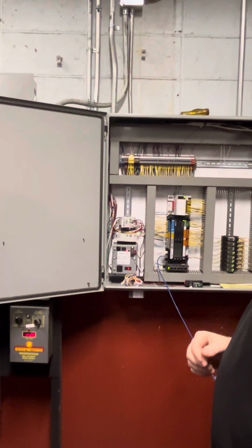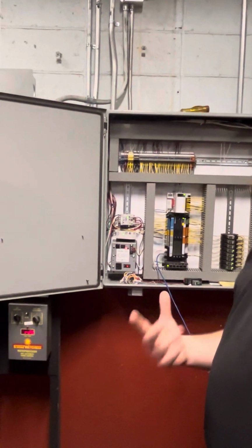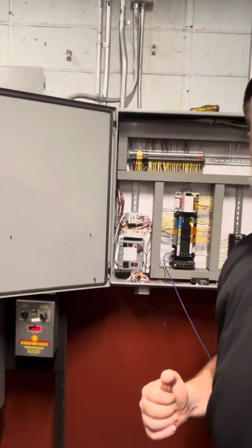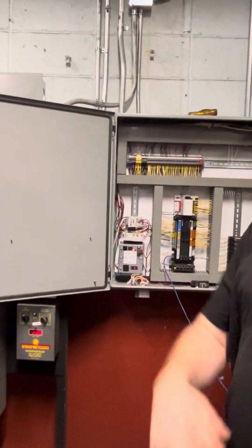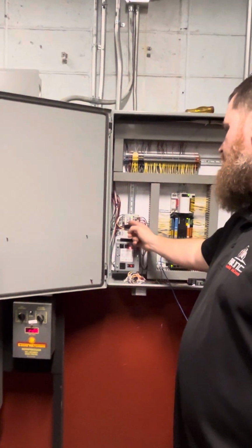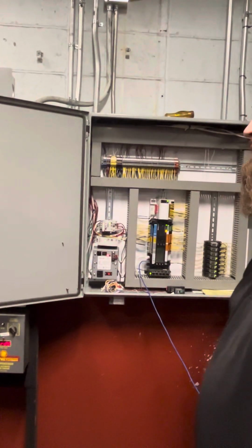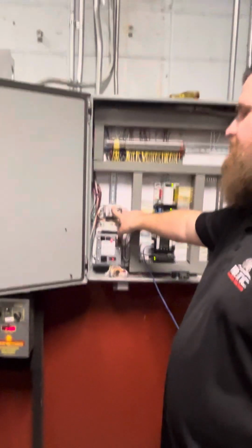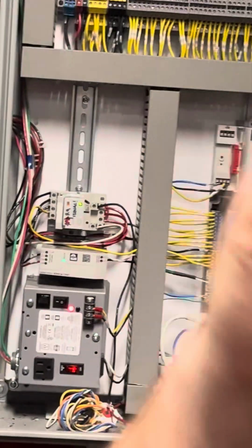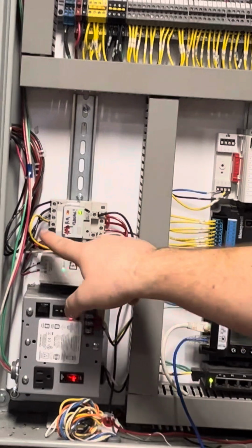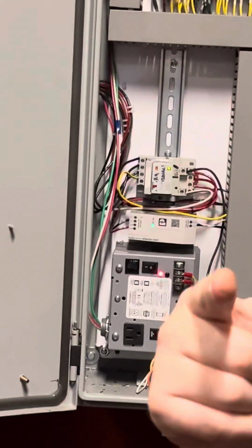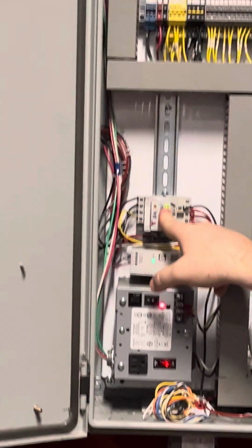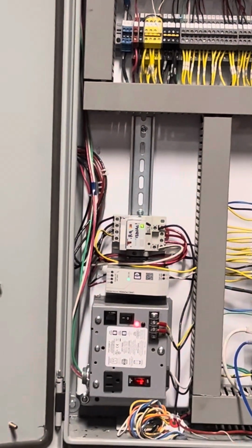Now, let's say that controller over there completely burned up. You now need to be able to bypass these controls. You can come over here and flip this little switch out right here. It doesn't matter if that green light's on or not. It's going to allow those boilers to run. As long as this is down, if that green light is on, it's engaged and those boilers are running. If that green light is off, we've got nothing.